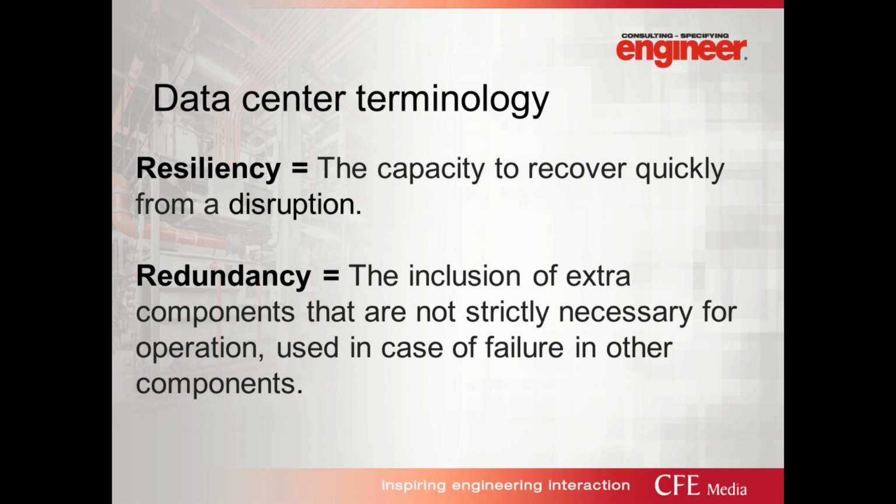So, the first one, resiliency, I think a lot of people from time to time would get this mixed up with redundancy. Resiliency is the capacity to recover quickly from a disruption in a nutshell. Redundancy can help you meet the goal of resiliency, but you don't necessarily need it. So you need to understand with your owners what exactly must be up, or what can you bounce back from. And it needs to be a holistic view. You're only as strong as your weakest link.